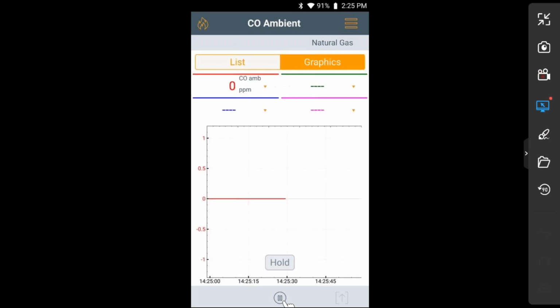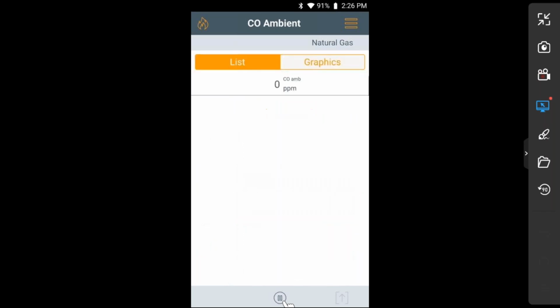Just like the other draft reading, we can graph this reading. And as I put some heat to this probe, you're going to see that the CO is going to jump up a little bit. Well, maybe not quite that fast, but there it goes. So you can see how it's pulling in a sample of CO, very little CO that I'm creating, but you can see the representation of the graph here as it's climbing and going back and forth.